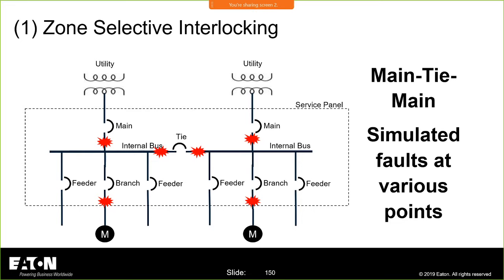Go back to the manufacturers. You're permitted to do that as part of 240.87. It says primary current injection testing or an equivalent means. And these are the reasons why that equivalent means is in there, because these things can be very complicated. This is not GFPE. This isn't, I'm just going to go out there, inject some current and be done. These things can be very complicated.